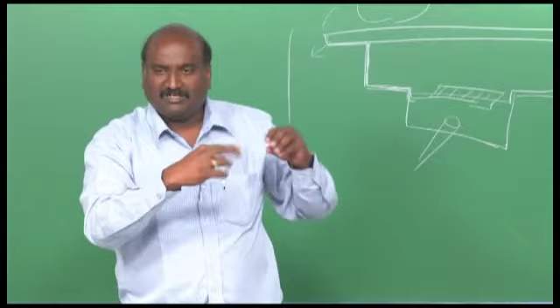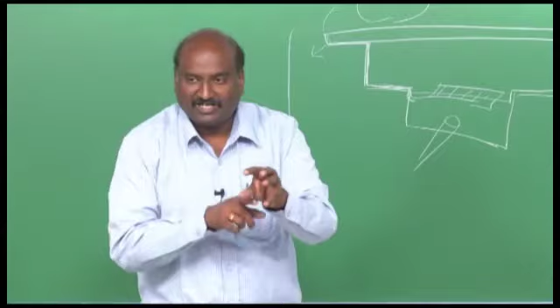If this entire liquid is continuously charged at some potential, and when it comes and touches this vessel which is fully grounded, this fellow is at some voltage and the bottom vessel is at some voltage. When this charged liquid reaches there, it is going to create a major spark. So you need to ground everything, the tank, the bottom receiver, the pipe, everything has to be grounded so that everything is at equipotential bonding.